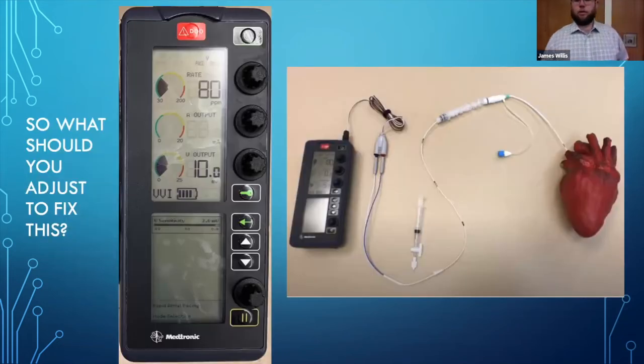And then if you really need to, you go back to your device as well and check your power, your battery, your connections, making sure the pacemaker wires are connected properly. And then confirm placement again, put your sub-xiphoid view, make sure you're in the right spot again, and consider changing the wire, or you can start transcutaneous pacing again, implementing your backup plan.